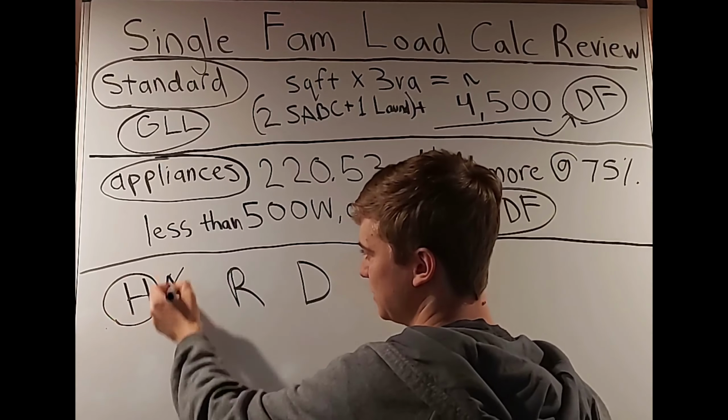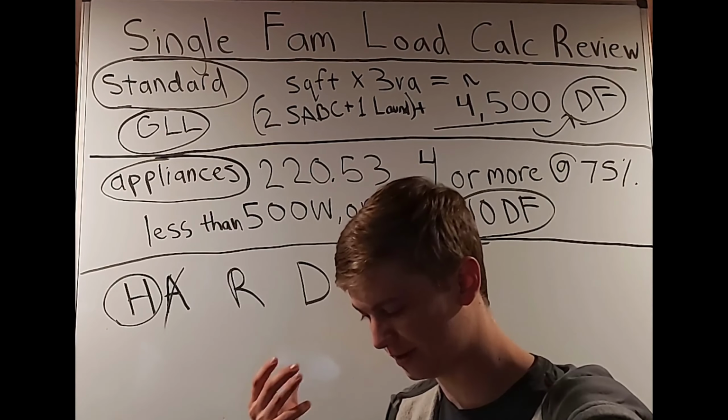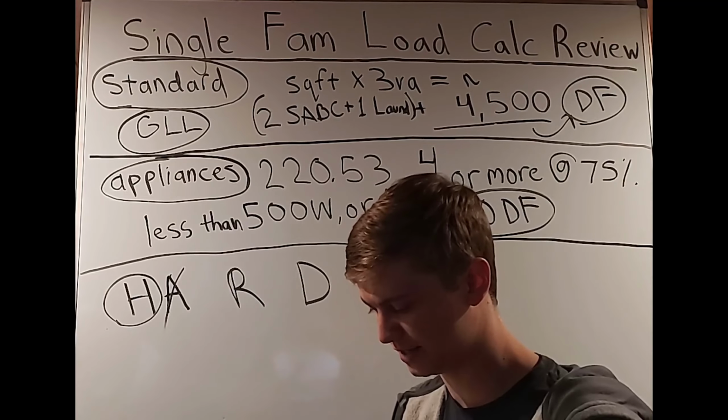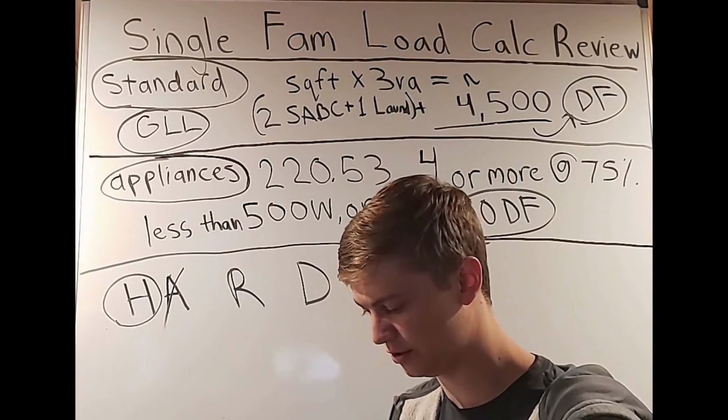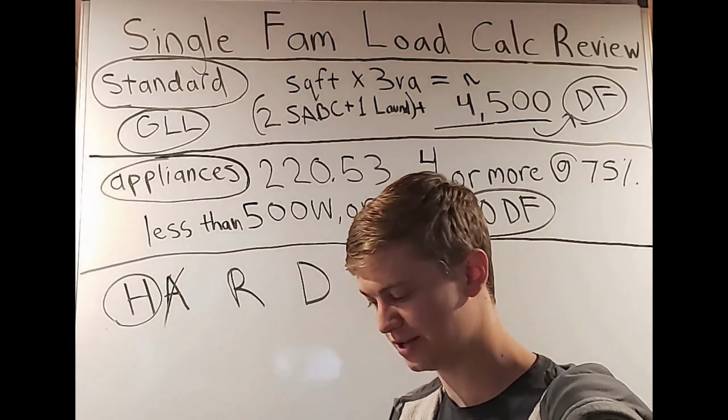I'm not writing this down because I'm just sharing that with you if you want to know how to use that. If you don't know, of course, column C is not percentage, that is actually a load. So they're telling you if you have 1 appliance and you're using column C, then you just have 8 kilowatts.